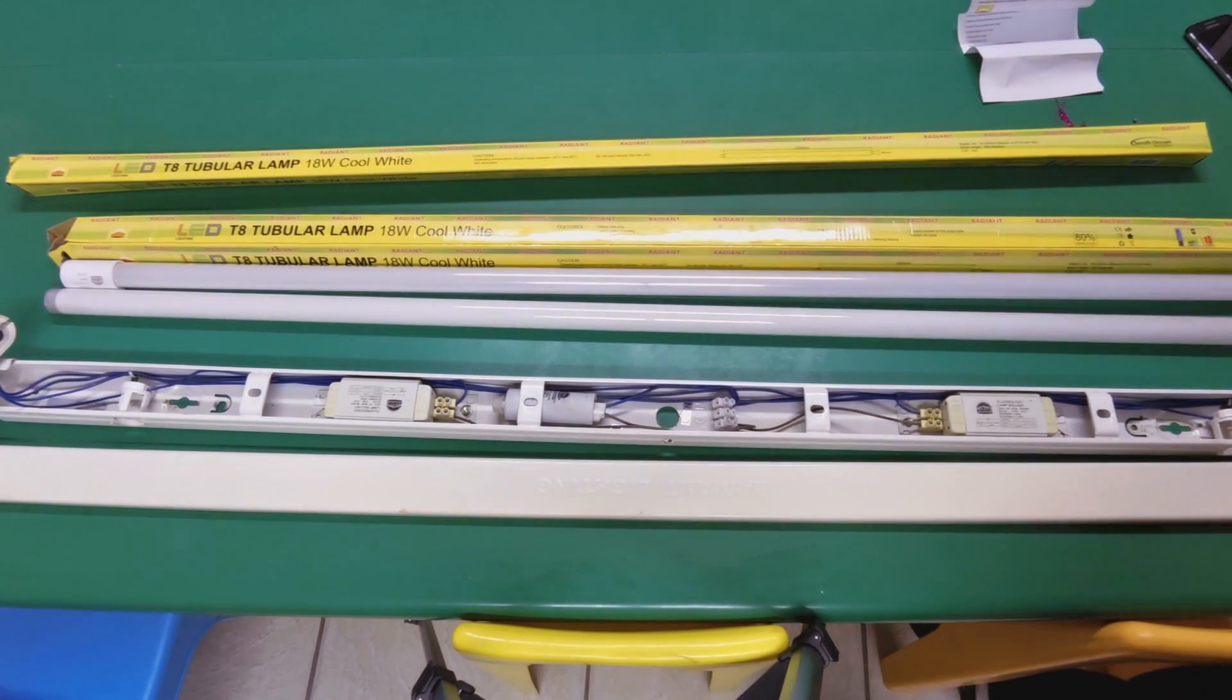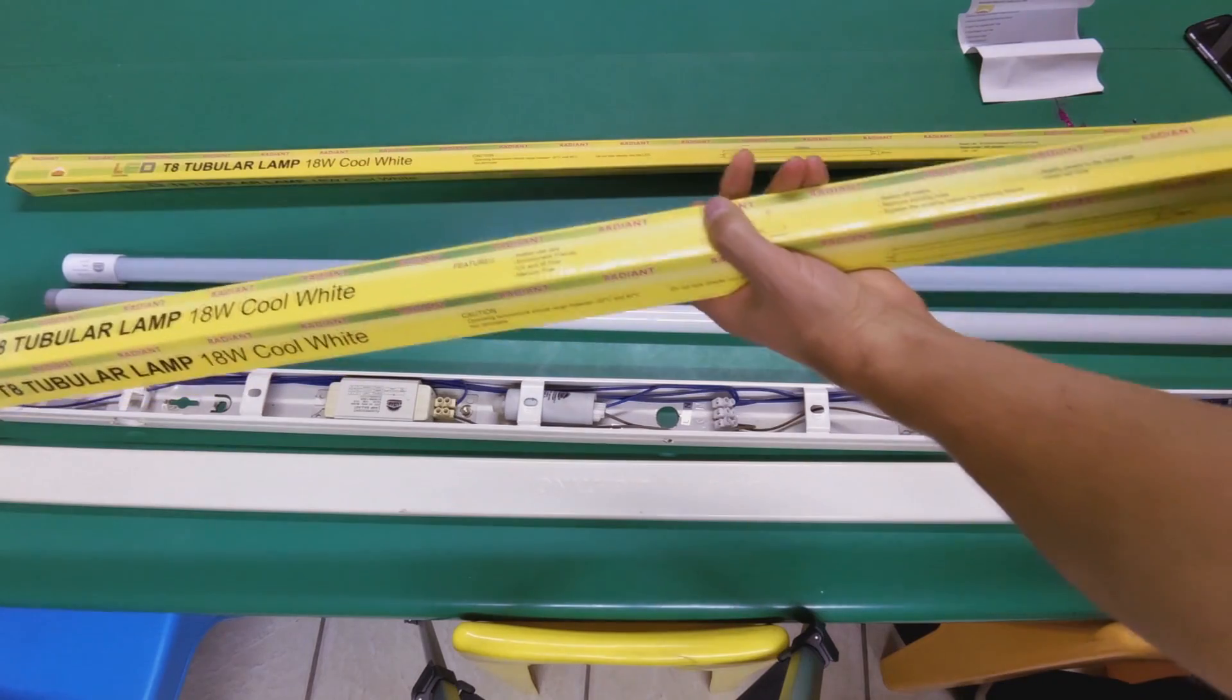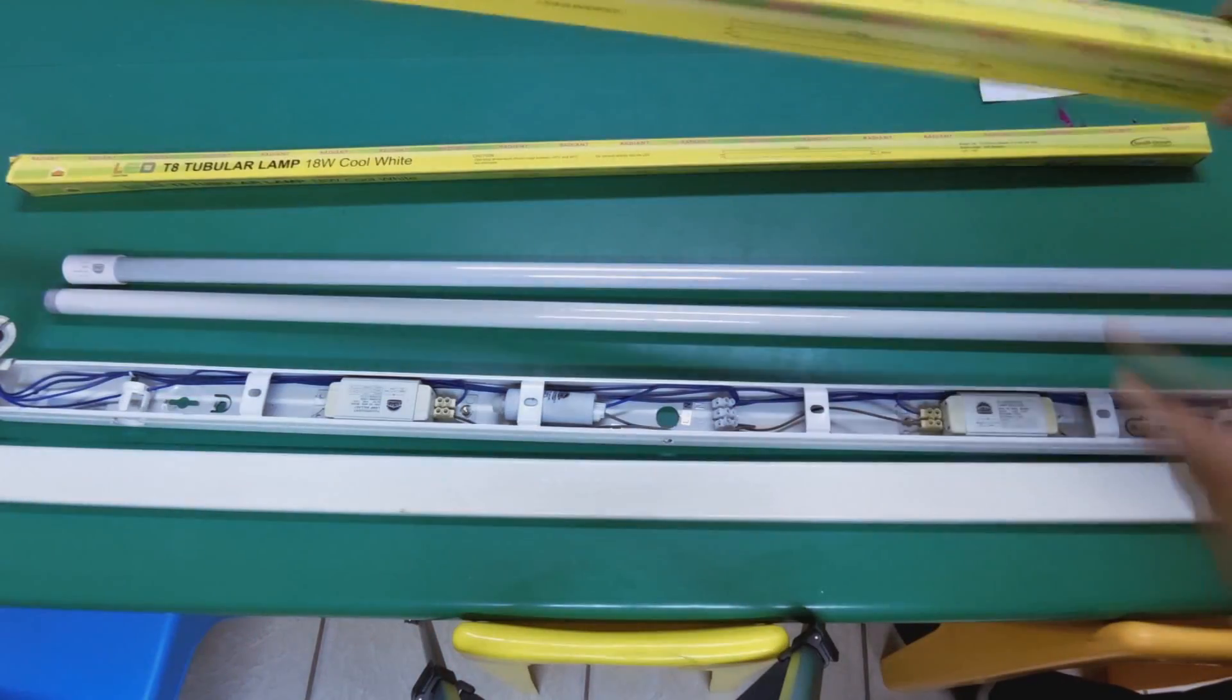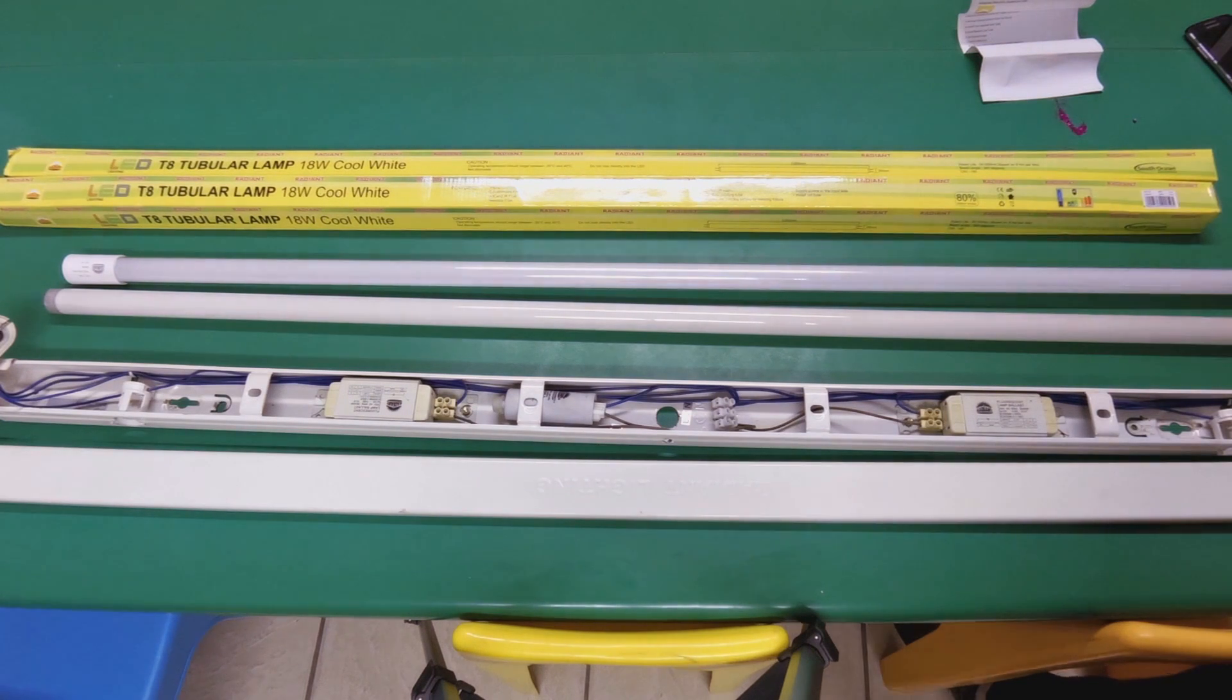Is it truly a saving? Yes, it is truly a saving, but we must compare the lumens. Lumens is a very important measure of lighting. And according to the manufacturer of this tube, they are rating their unit at 18 watts, the temperature is 4500, at 1440 lumens.